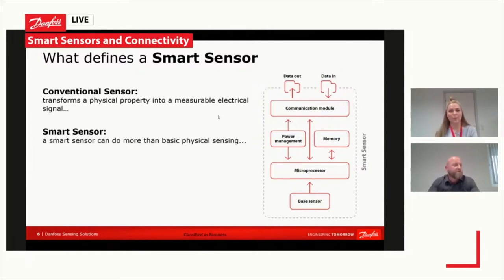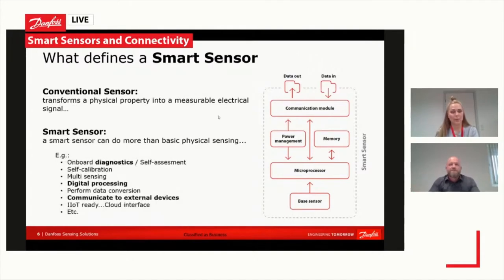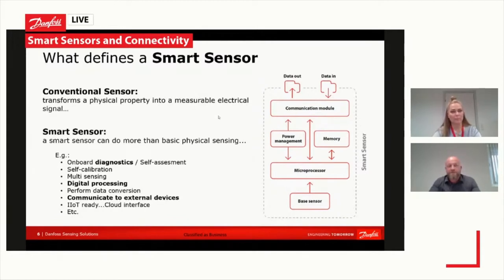Depending on the protocol, this could also be data-out only. Some examples of new features include: on the diagnostic side, information about what the sensor has experienced over its lifetime — self-assessment logic that can be very beneficial when problems occur on the application side. There are also self-calibration features, such as application-specific or installation-point-specific algorithms that trigger certain calibration steps. Multi-sensing is another interesting capability, where a single sensor can detect more than one physical property — combined pressure, temperature, humidity, or gas sensing, for example.